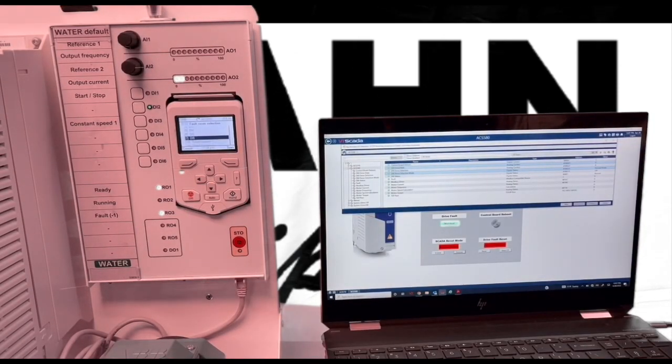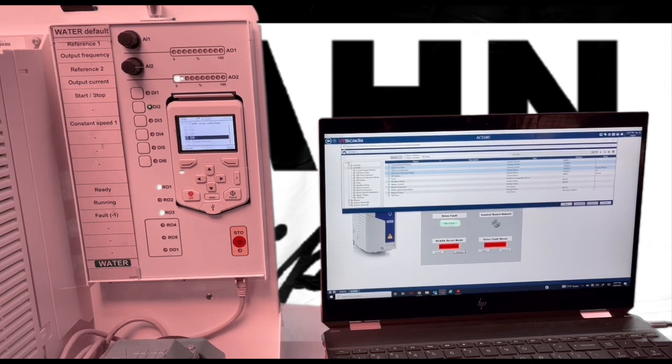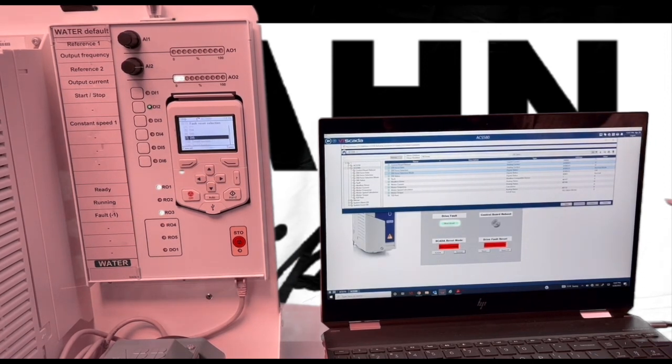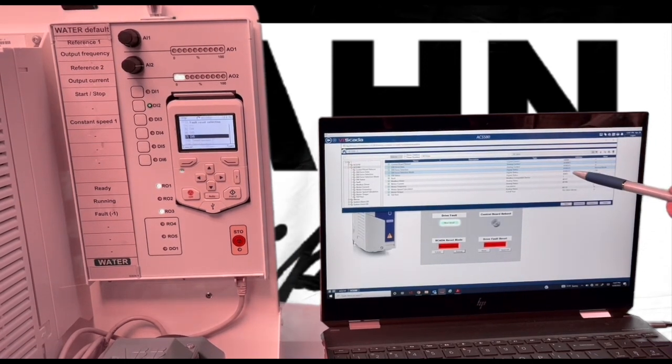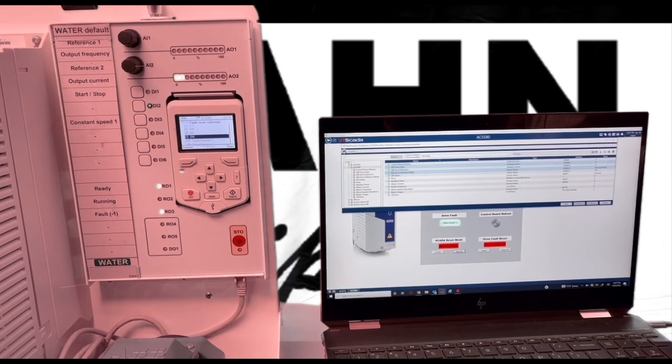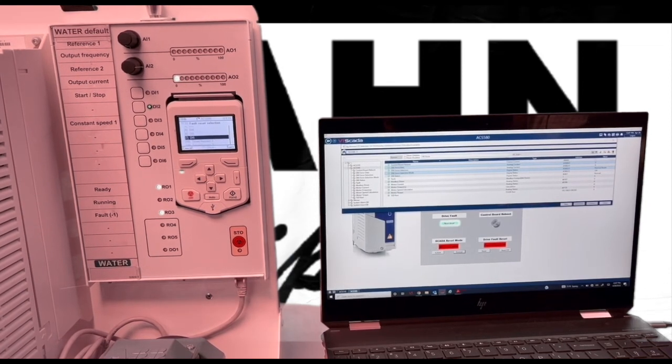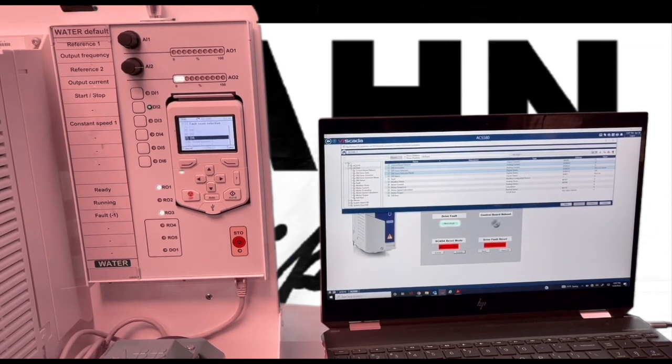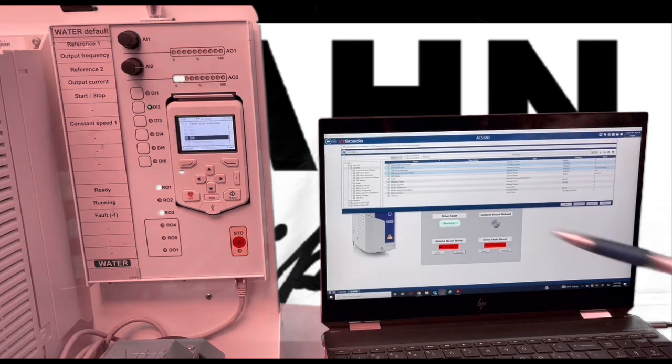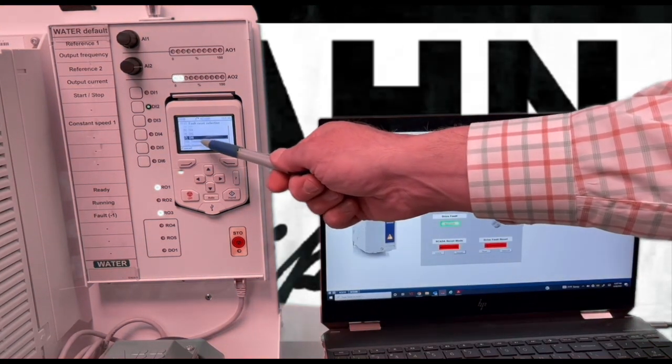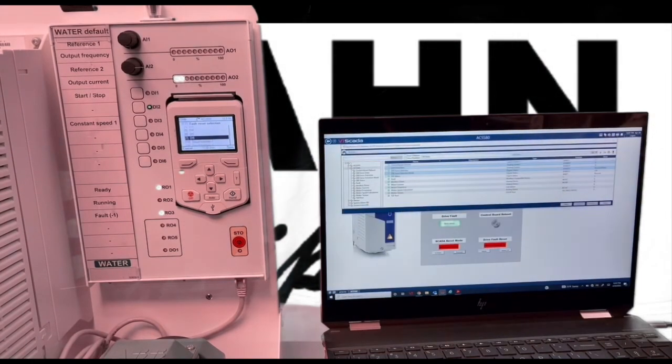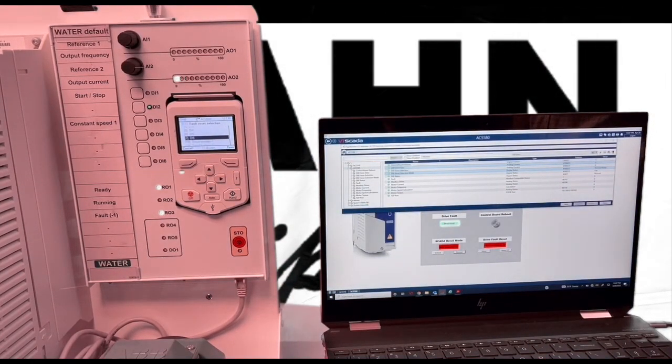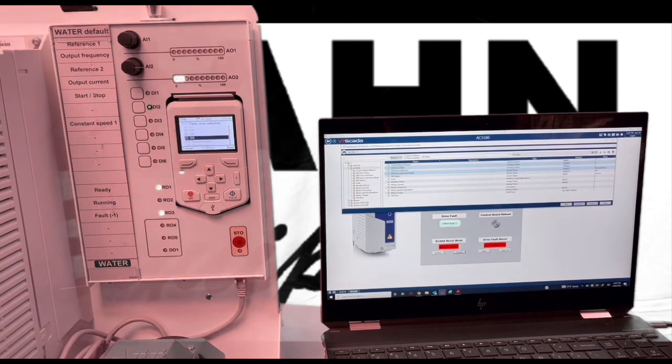First we put the VFD into SCADA mode using Modbus Register 41003 bit 5. Then we set the digital input for the VFD as a fault reset button in parameter 3111, resetting the parameter to DI6. Then we can force DI6 into a reset state via SCADA Modbus Register 41004 bit 5.